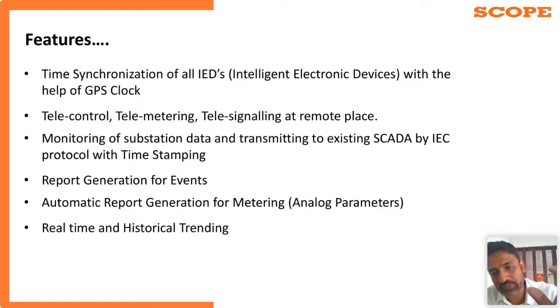Suppose you want to use this RTU's signals as a master clock and synchronize other nearby systems, like the relays or any other local monitoring system. You can use the signals from the RTU clock to sync those things, so you don't need to purchase a separate GPS clock system to synchronize these relays. Many RTUs have these features.